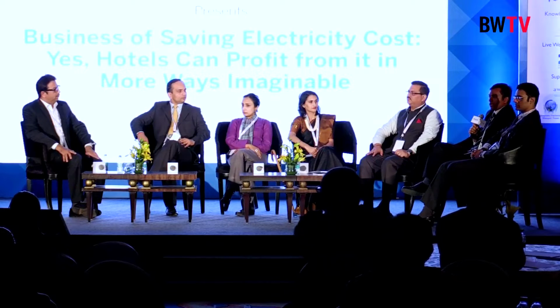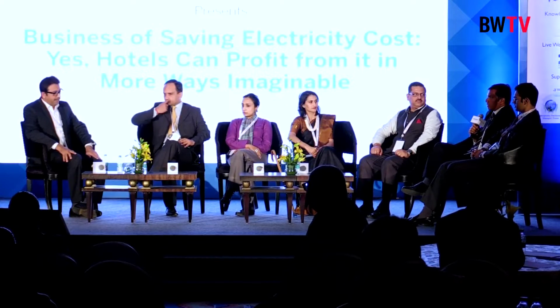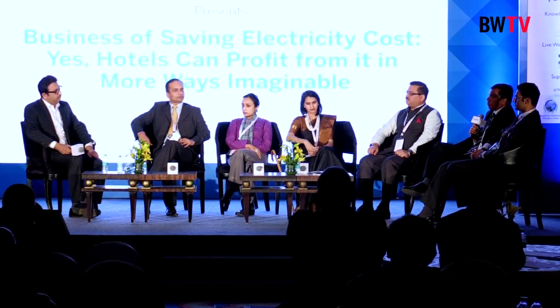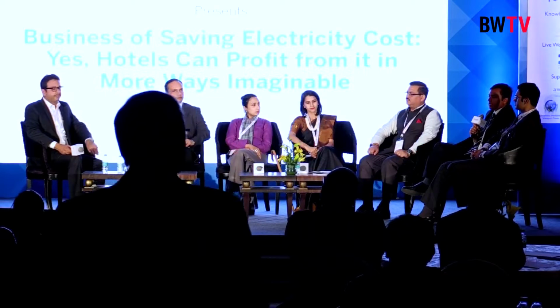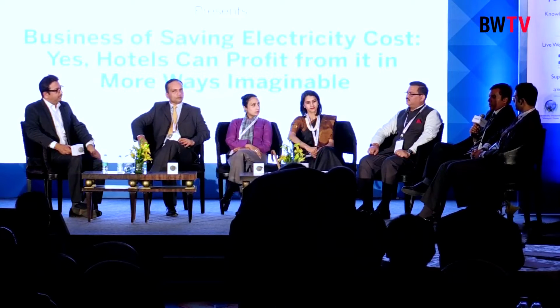And it's not only the per unit cost. Another biggest advantage of going with short-term open access we found is power outages, and the DG running hours have come down drastically, to be very frank. Discoms can't cut without intimating the hotels or commercial establishments going with open access. So it directly impacted the HSD cost and the DG running hours. That was a big achievement.